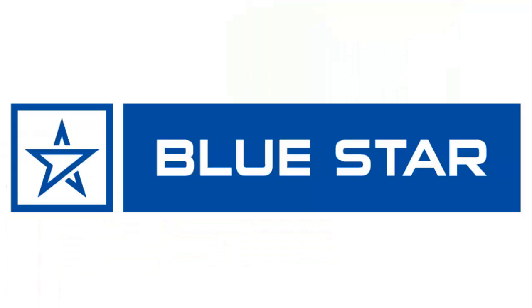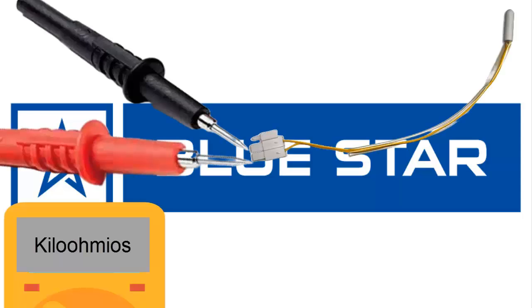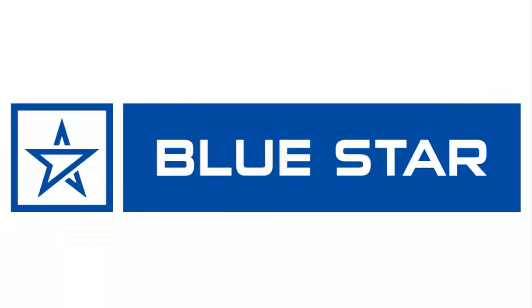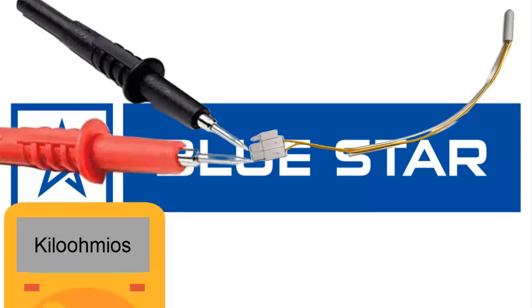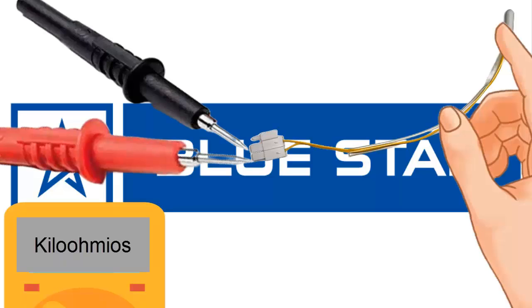6. If the error persists, turn off the unit, disconnect the sensor, and measure its electrical resistance with a multimeter set to the kilohm scale. The measured value should never be 0 or infinite. Otherwise, replace the sensor. Remember that when rubbing the sensor with your hand, the resistance value should decrease. If not, replace the sensor.